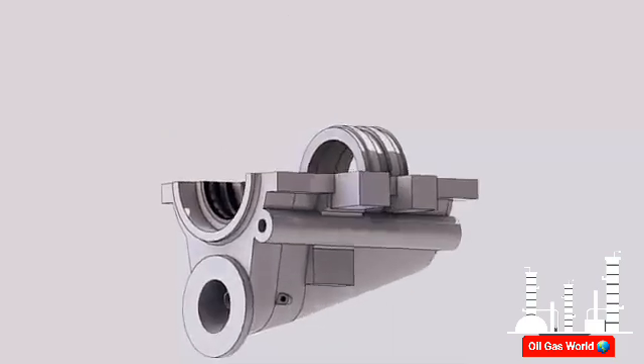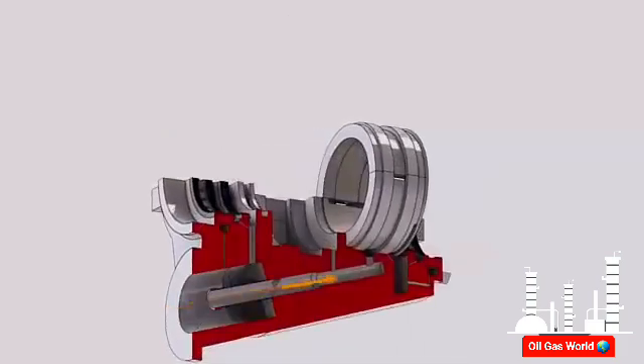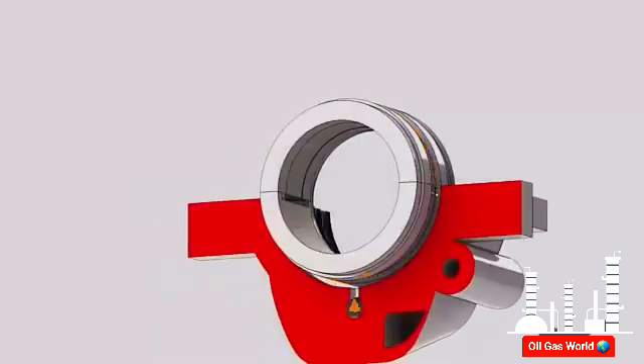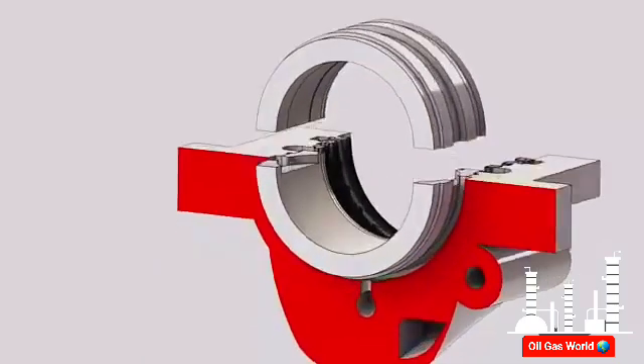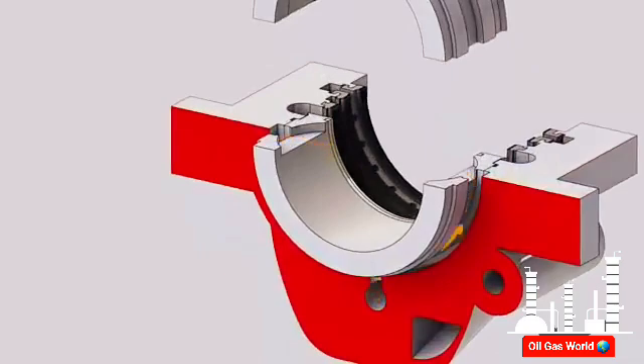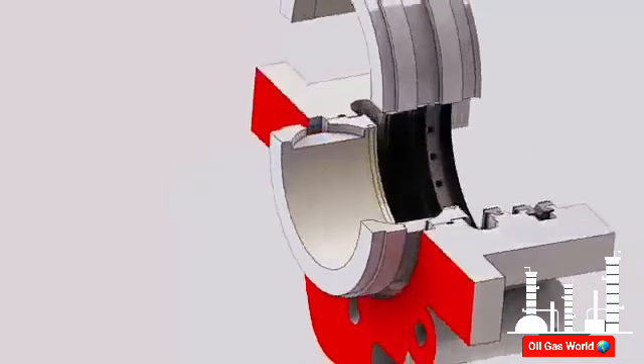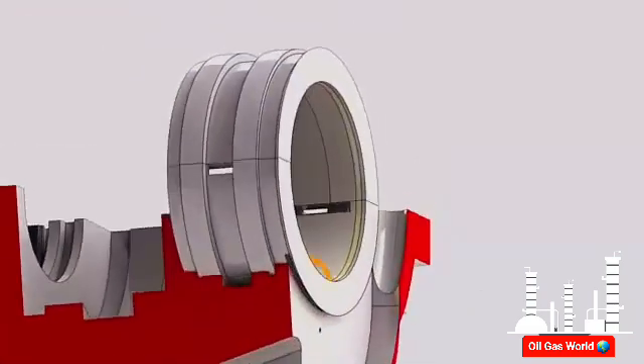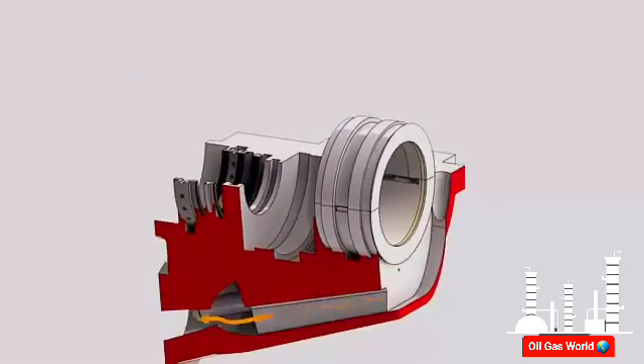For lubrication, oil is supplied through the oil feed pipe to a port in the lower bearing housing, where the oil fills an annular space around the liner and is admitted inside the liner through two grooves machined at the horizontal matching edge. Oil is drained through the vertical drain slot at the bottom of the lower liner half to the journal drain cavity, down to the oil drain piping.